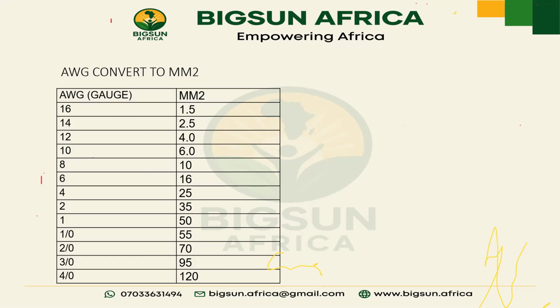Does anybody have a contrary opinion? Our final answer is we are using 4 mm, sir. No, let's start from the VDI first. 100 amps times 9 times 1.3, that's the safety factor, over 48 times 2.